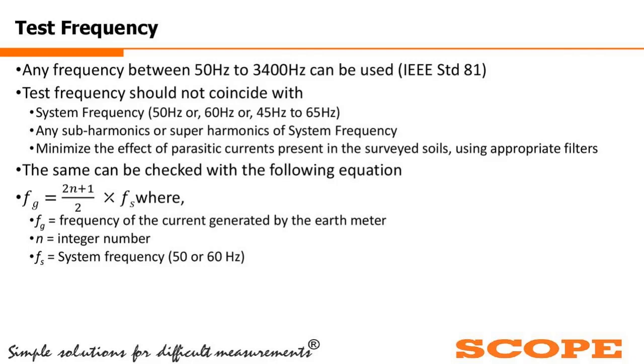So, the test frequency should not fall into the superharmonics or the subharmonics of the system frequency. Like it should not be 10 hertz or 20 hertz, or it should not be 100 hertz or 150 hertz. Direct round figures are not the ideal figure. So how do I understand whether the test frequency offered by the OEM of the earth resistance meter is suitable for my system, is a good frequency or not, whether it is in line with IEEE standard 81 or not? There is a simple formula.